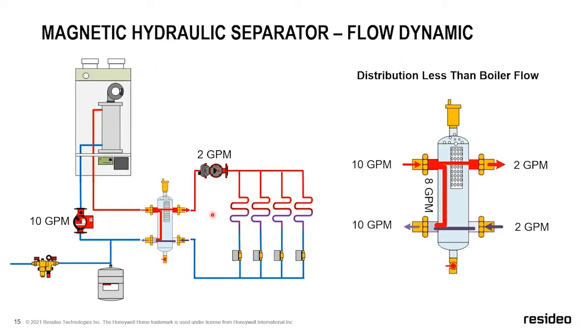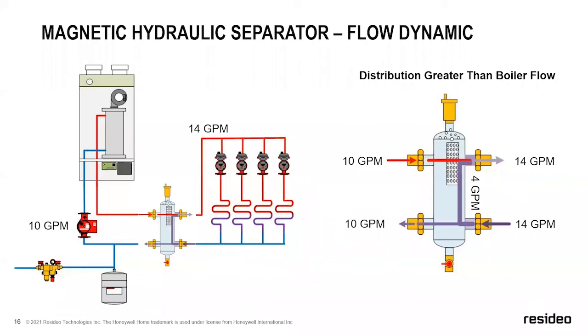Like if you're doing manifold actuators, you typically see a flow rate lower on the system side than you do on the boiler side. For those of you in markets that zone pump, you're going to get a slightly different dynamic. You've actually got the opposite thing normally taking place from my experience than if you're using a single pump with zone valves. So in this example, we're still living with this 10 gallon a minute flow around the boiler. But what's taking place is, now let's say we got a pump on every single zone. Usually in this example, from my experience, these pumps are slightly oversized unless you've got circuit setters really driving the flow to where it should. But in this example, we're driving 14 gallons a minute with all 4 pumps turned on at the same time.